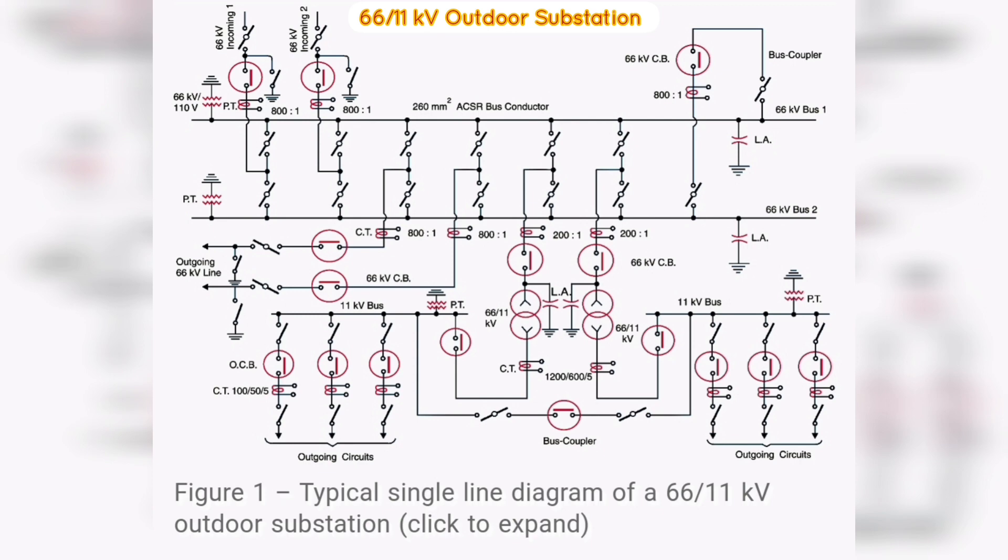There is also an arrangement to step down the incoming 66 kV supply to 11 kV by two units of three-phase transformers, each transformer supplying to a separate bus bar. Generally, one transformer supplies the entire substation load while the other transformer acts as a standby unit.